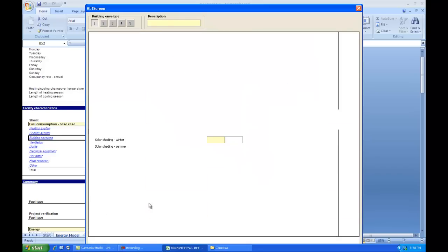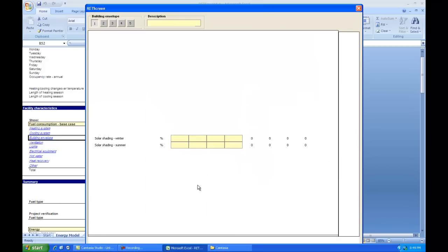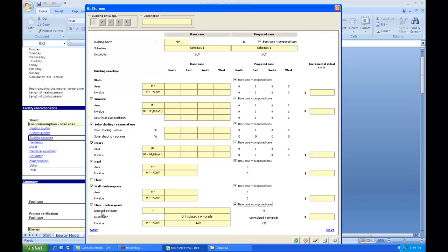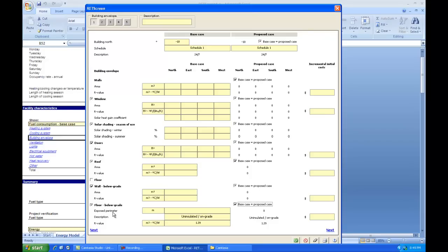Similarly, the floor below grade, we click that and open that up. And the number of boxes get bigger and bigger as we go. So the floor below grade is going to lose some heat, but not a whole heck of a lot compared to certainly a cold floor above grade. Notice on floor below grade, the number that we enter is not the area of the floor as it is in all these other boxes. It is the perimeter of the floor. The reason that we work with the perimeter for a below grade floor is the perimeter is what matters for heat loss. The floor doesn't lose any heat in the center of it. The floor loses heat all around the edges. The edges of the floor are what are exposed to the cold ground.